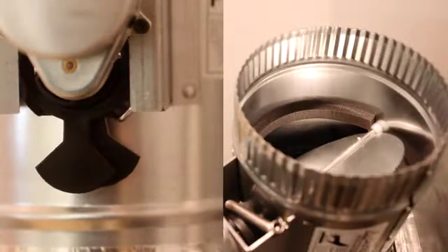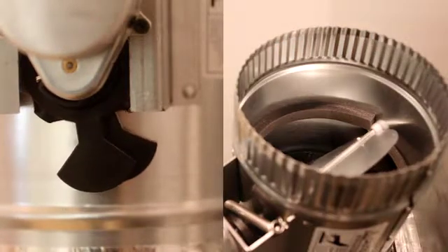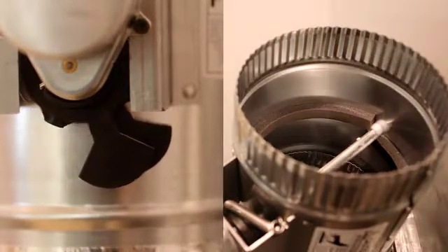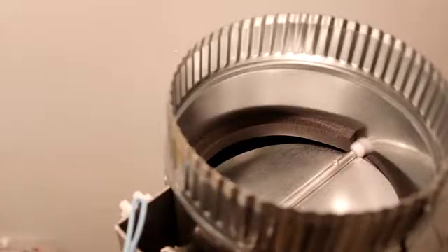In powered mode, the damper will open fully to bring in extra outside air when the thermostat is activated. In the unpowered mode, the damper will remain in its partially closed position to continue to deliver a required minimum amount of outside air if your air handler's fan is set to on instead of auto.